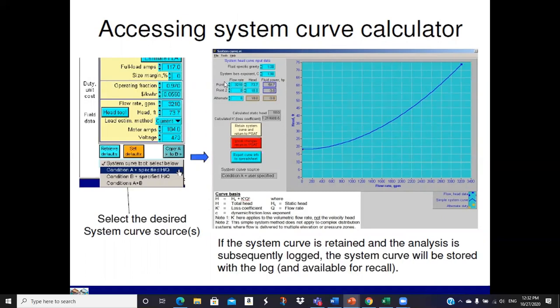And so we put in a specific gravity because someplace in here it calculates pumping power, the fluid power in horsepower. So it needs a specific gravity for that power calculation. The exponent that you want on your equation, it's a little hard to see there. And then you put in two points that are on the system curve, and bingo, it spits out the static portion of the head right here, and then the loss coefficient, which is just a constant that goes there. The flow raised to whatever power you put in, and that's your system curve. The mathematics is very simple, but it's handy to have a calculator to do that for you.